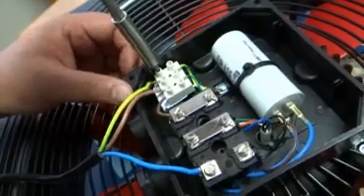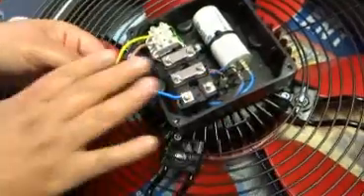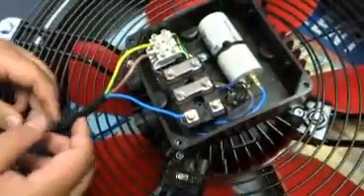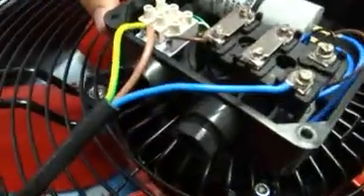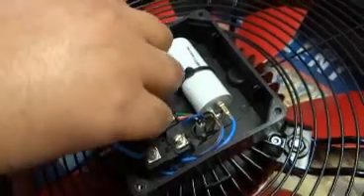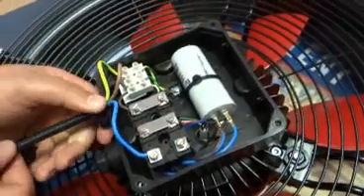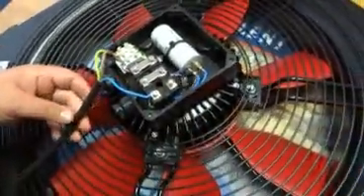Just make sure that all your wires are securely fastened. For illustration purposes we connected our three-core cable directly to the connection box, but in practice it must come in via the gland, using a 20mm gland to fasten your cable. You can also adjust the length of your wiring to make your connection box look neat.